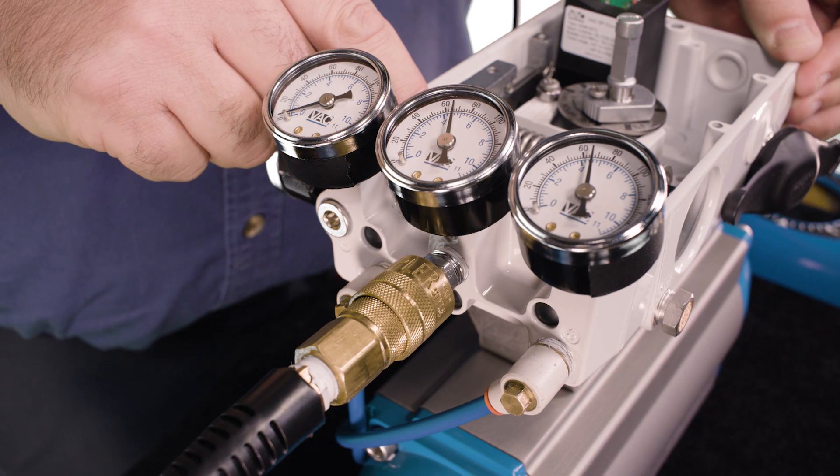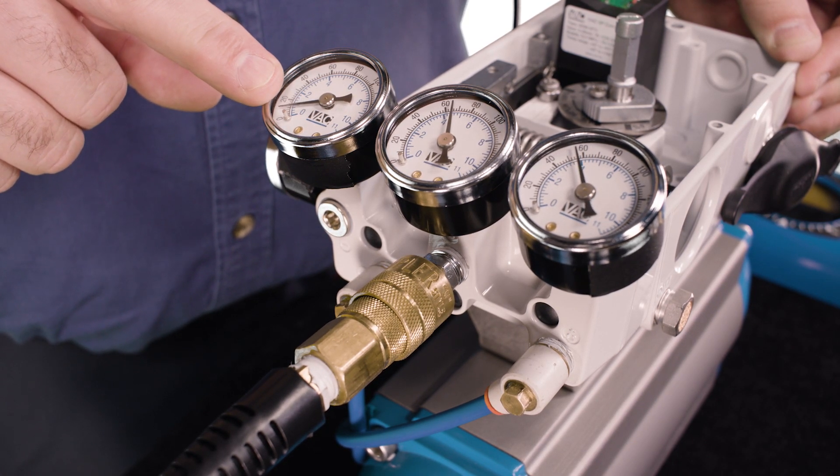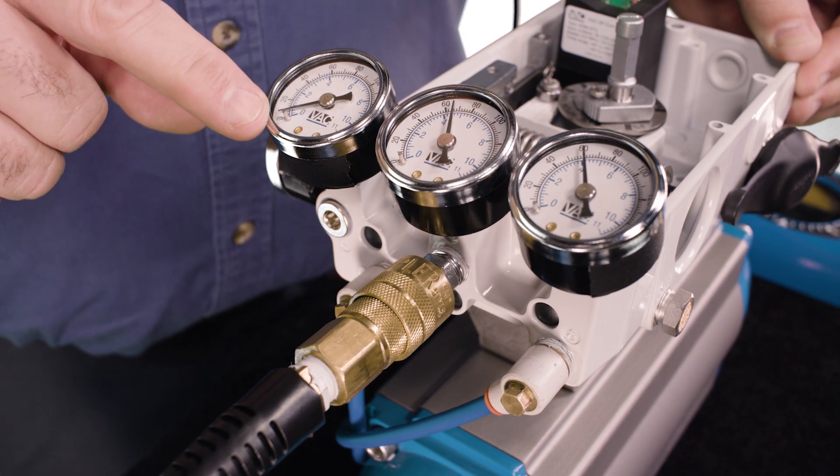You can move the balance arm toward the positioner housing to bump the positioner. Watch the C plus gauge needle. It should take three to five seconds to reach zero psi.